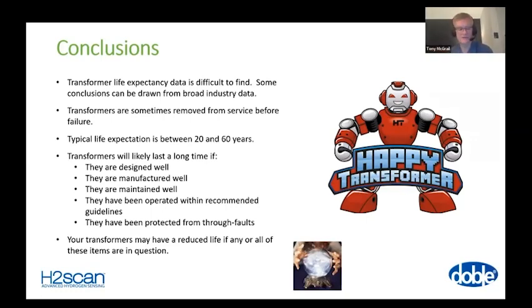We've had a transformer fail recently where they had undersized the leads from the bushings, what's called the HV lead, earlier, to the windings, and they were failing in service. This should have been picked up at the factory inspection test.